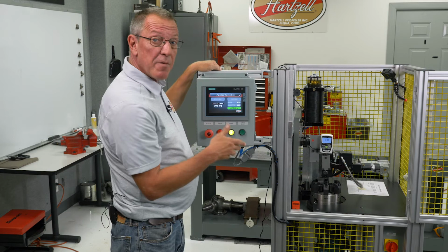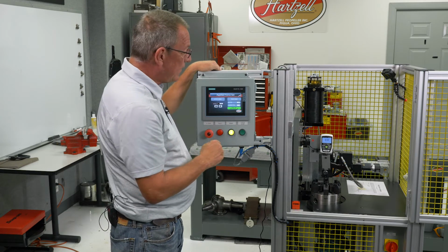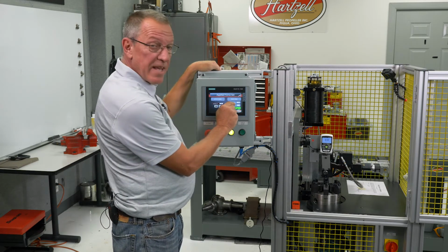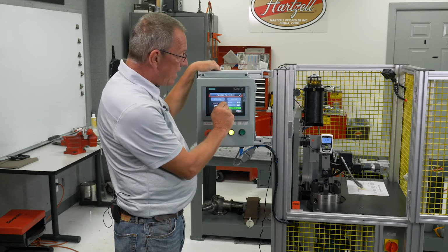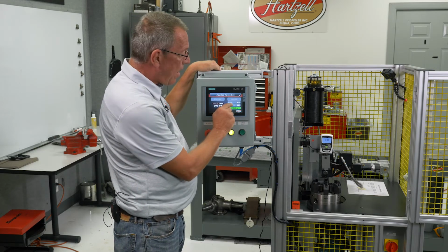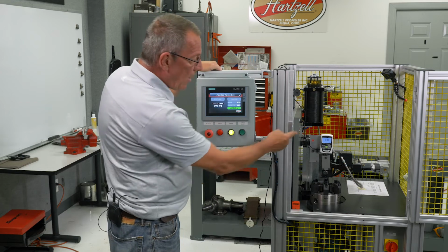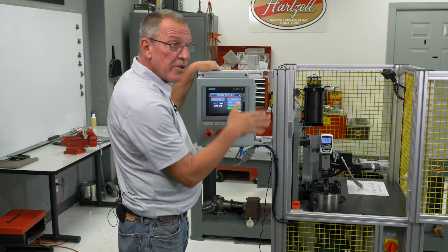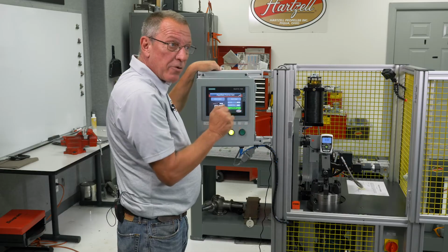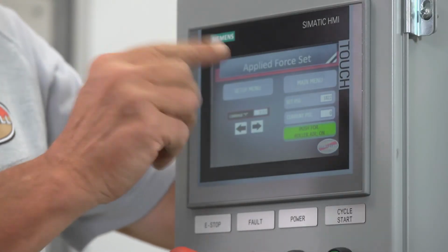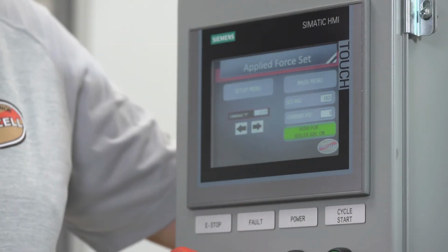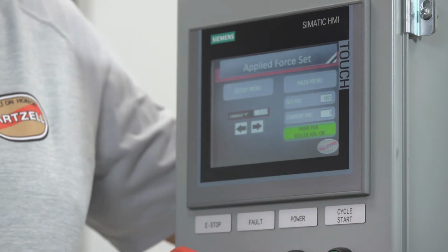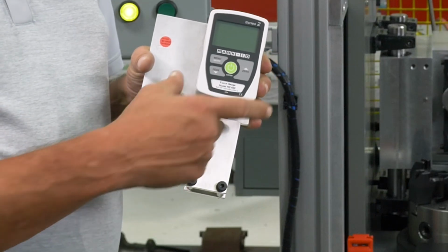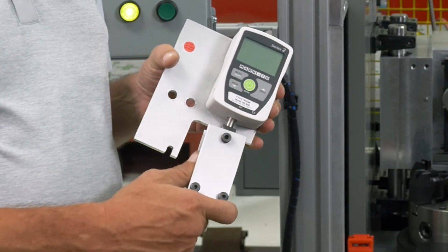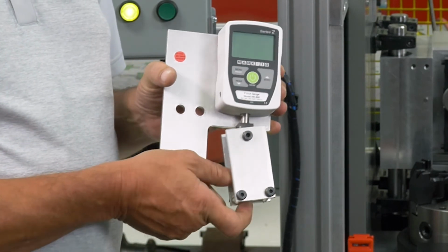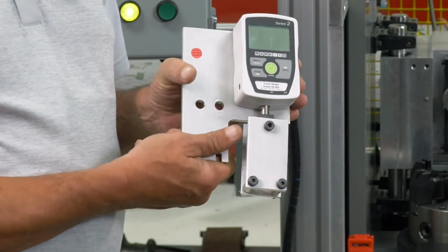Now, if I was out of tolerance just a little bit, for every 7 psi I add to the set psi value, it gives me 1 pound force on the gauge. So if I need to move up and down a pound or two, I can do that just by adding 7 psi or reducing it by 7 psi to get the number a little closer. With the force calibration now complete, remove the force gauge and associated bracket before proceeding to the next steps.